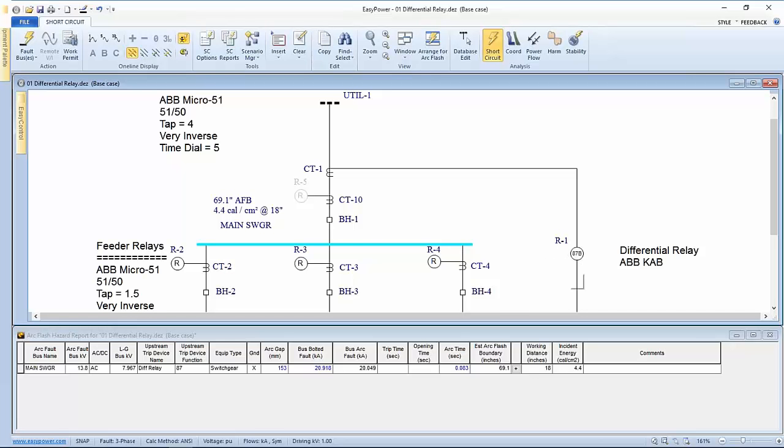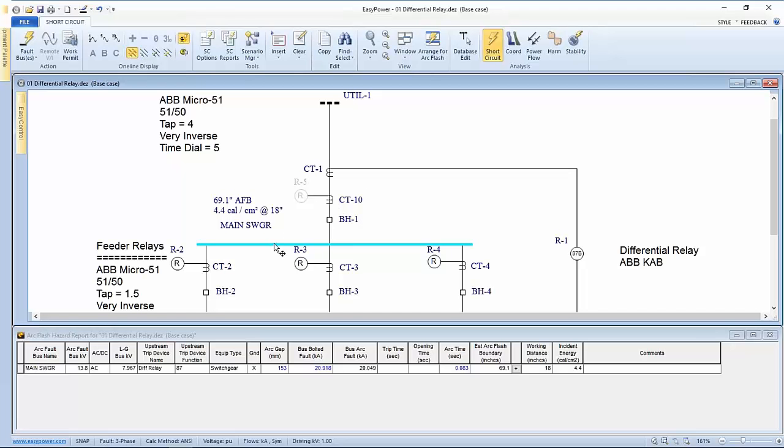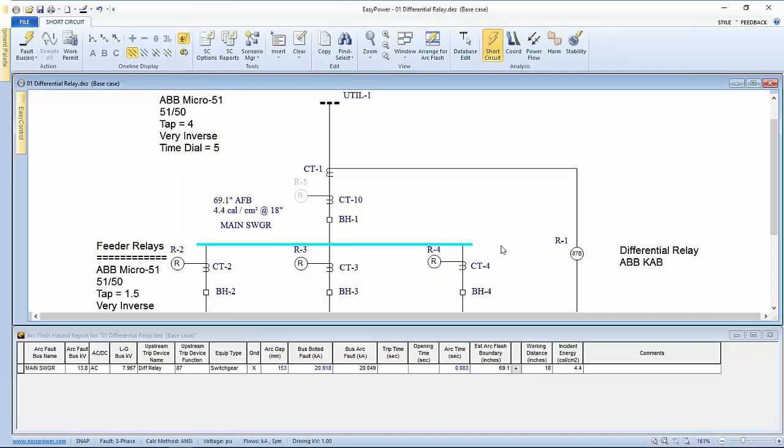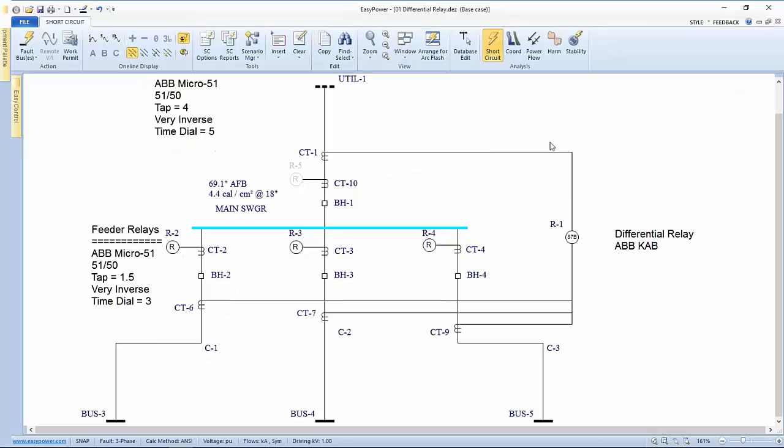This particular energy would be utilized in the arc flash work permit that would be utilized, part of which the procedure would say, when we're working on this bus, and we have the ability to detect a differential arc. I guess I take that back. By utilizing this setup, we actually could label this bus, because this is the arc flash protection for that bus at all times, as long as there's no way to disable the relay. Hopefully I didn't muddy that up too much.